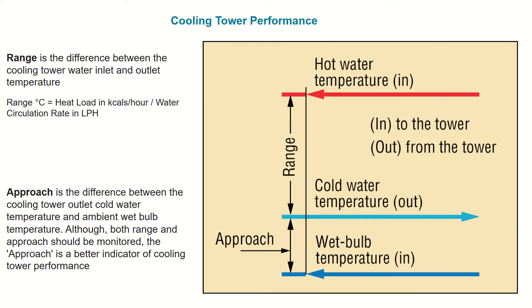Range can also be calculated using this formula: range is equal to heat load in kilocalories per hour divided by water circulation rate in liters per hour. The second parameter is approach.